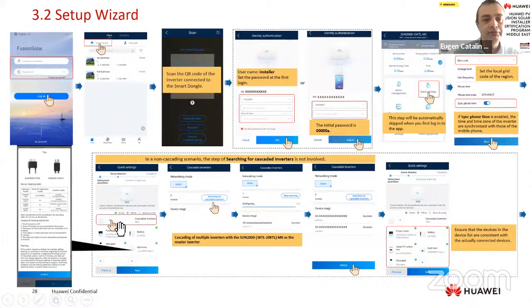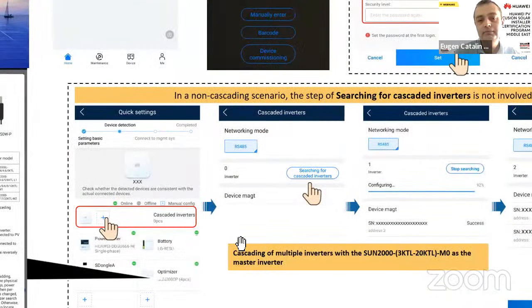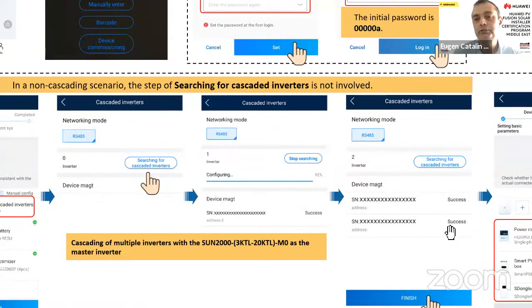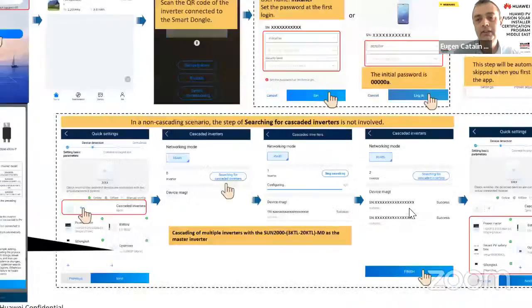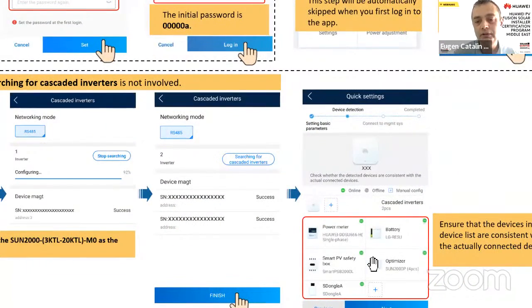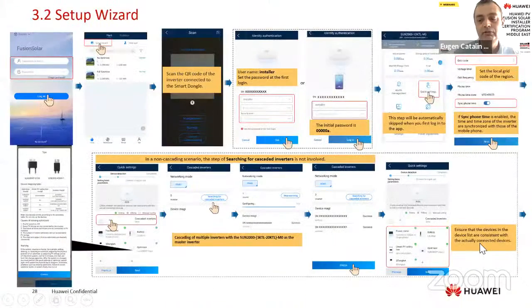Second, the next page will be to check all the connected devices. The new residential product, L1, M1, will auto-detect all the devices if they are correctly connected: battery, meter, optimizer, smart dongle. All of them should be green here if you connected correctly to the inverter. If you have a cascading scenario, from this page you need to do it manually. The inverter will not auto-detect the slave inverter. You need to perform this cascading scenario, follow all the indications, and in the end, you will have 1, 2, depending on how many inverters you connect in cascading. And after that, we will have a complete inventory with all the connected devices, and also with the cascading inverter number here. Okay, after that, we'll go next.